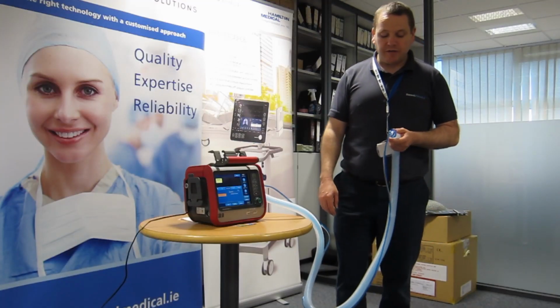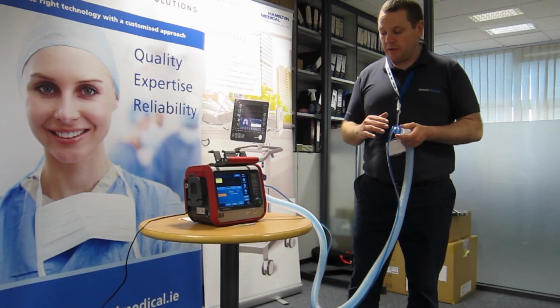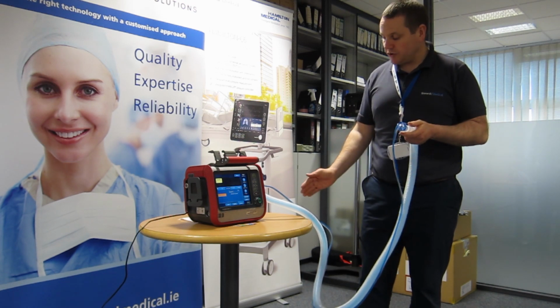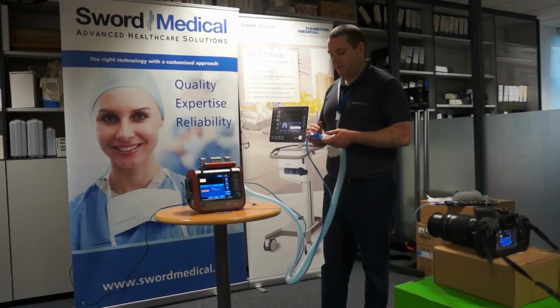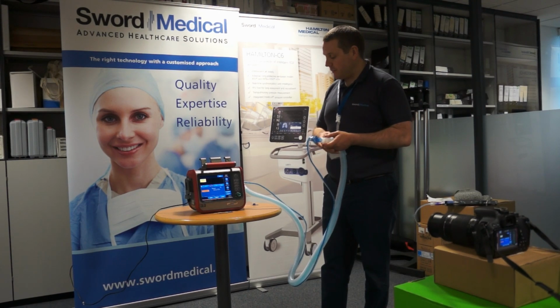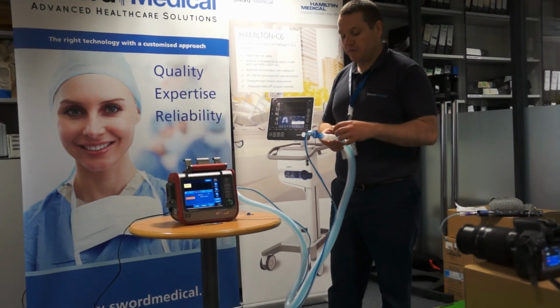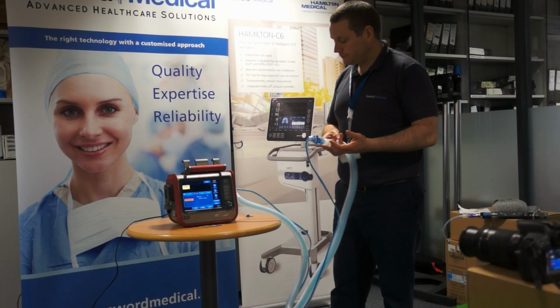So the ventilator is going to generate 4 different levels of flow. It knows how much flow it's generating, so it knows what the sensor should read. And then halfway through it's going to ask me to turn the sensor back around again, and it's going to do the same manoeuvre in the opposite direction.